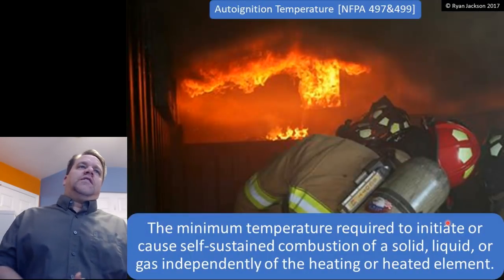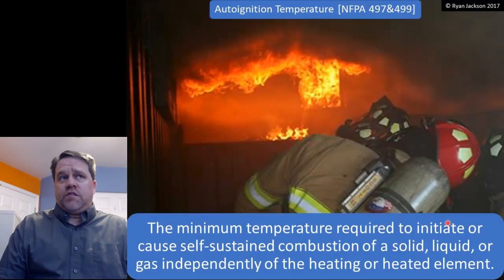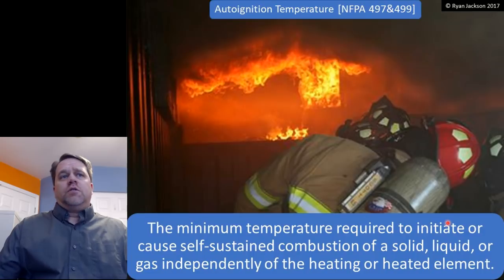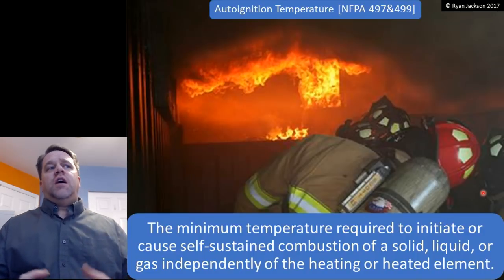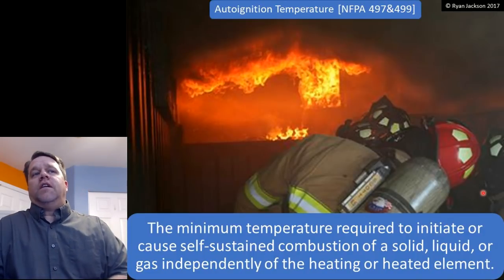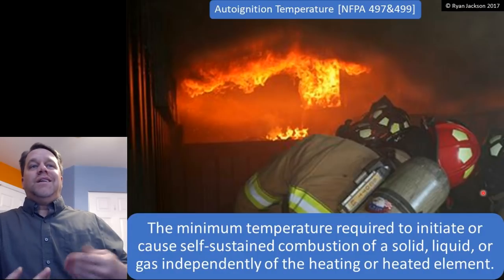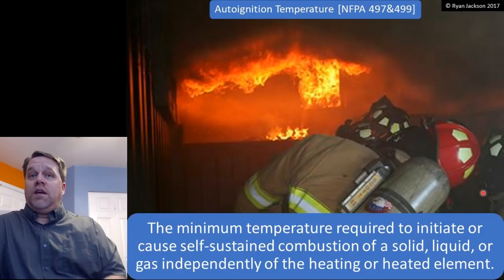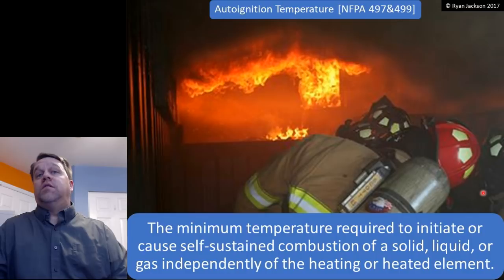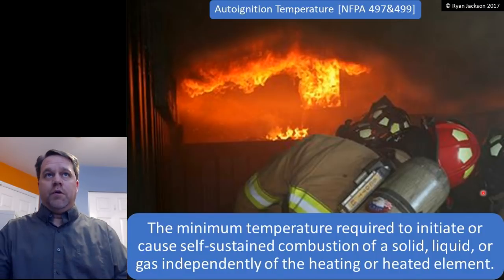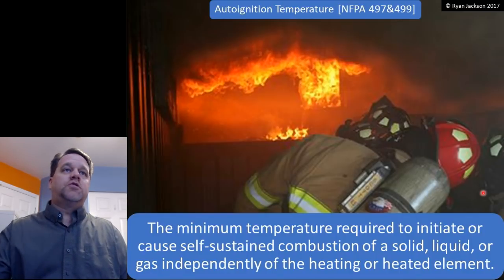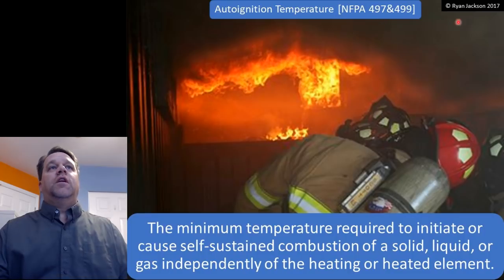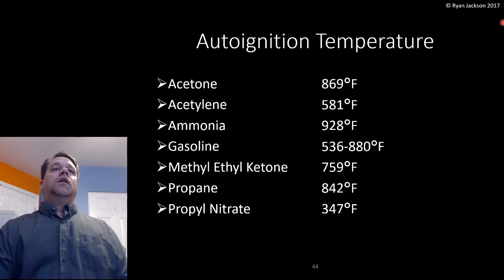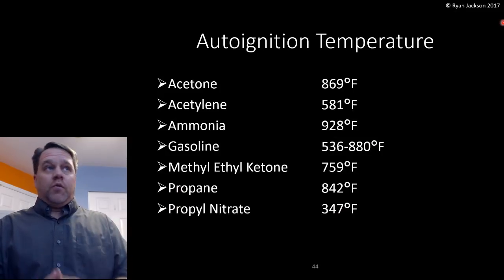The last characteristic that we need to know about is the auto-ignition temperature. The minimum temperature that's required to initiate or cause self-sustained combustion of a solid, liquid, or gas independently of the heating or heated element. How hot do you need to get the material before it goes kaboom? That's the auto-ignition temperature, defined in NFPA 497 and 499.